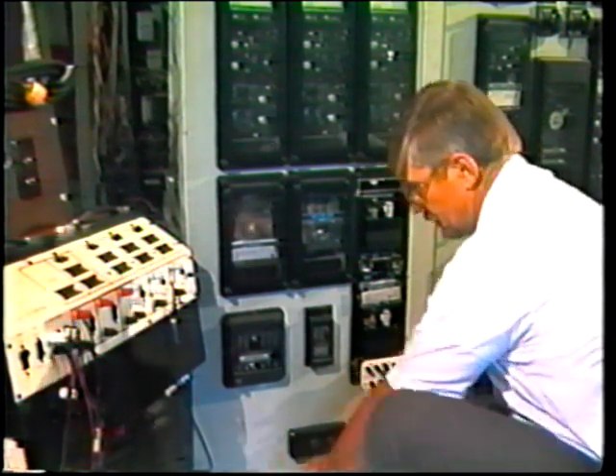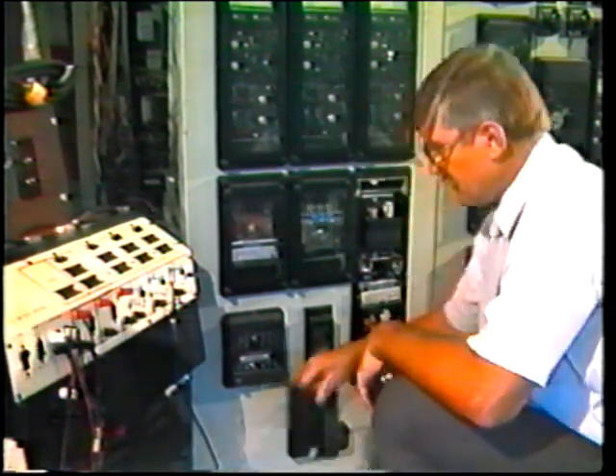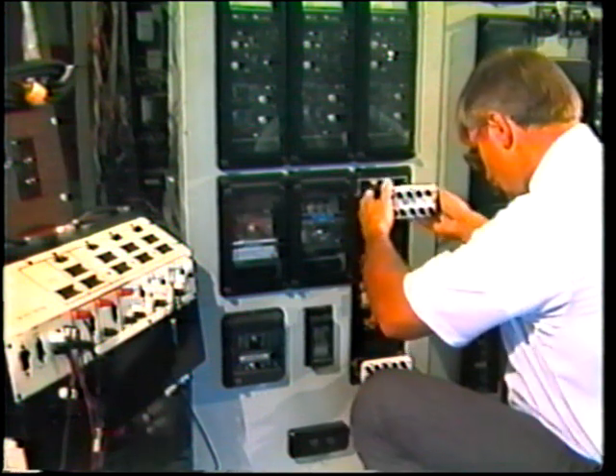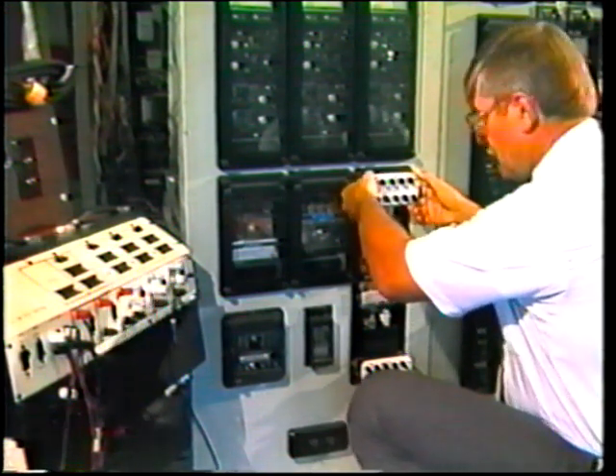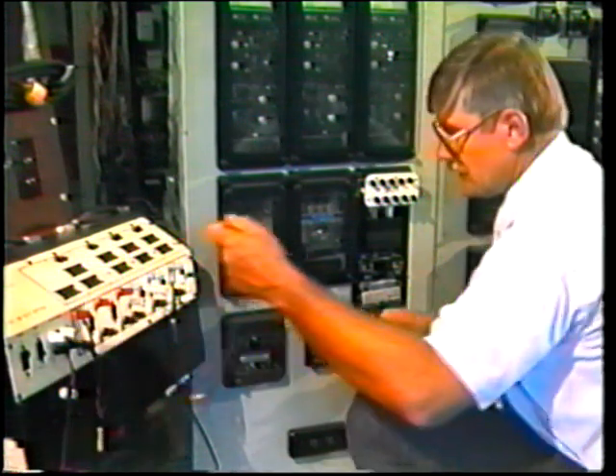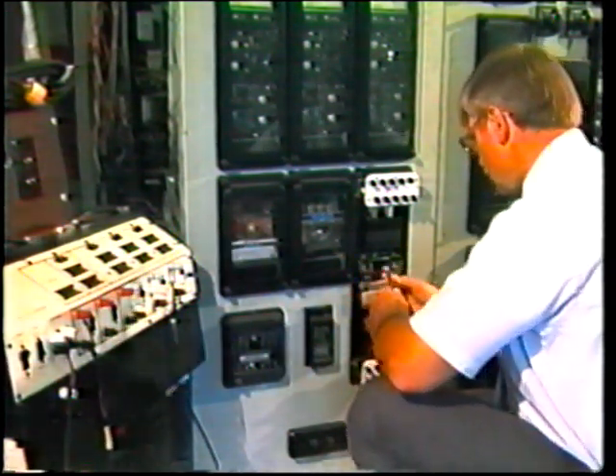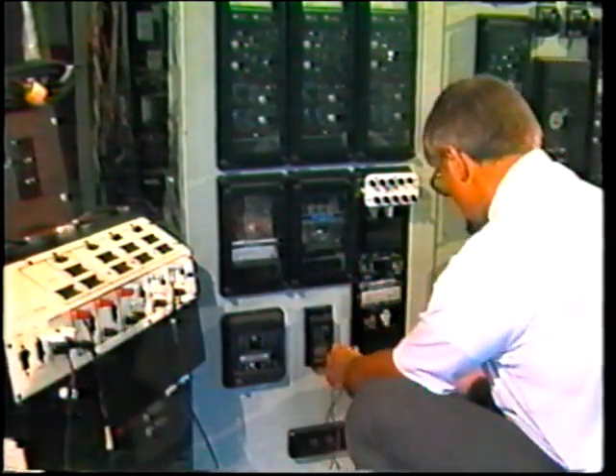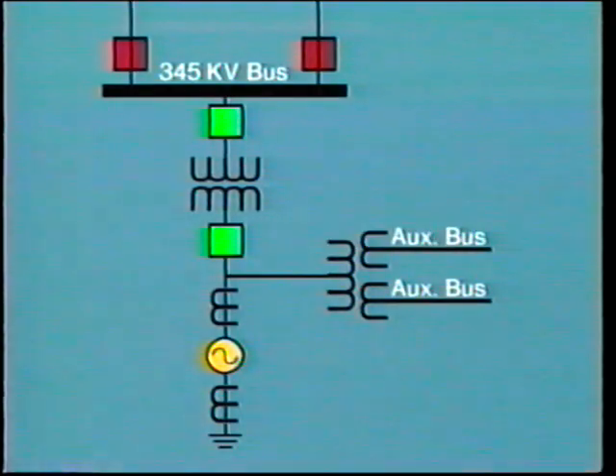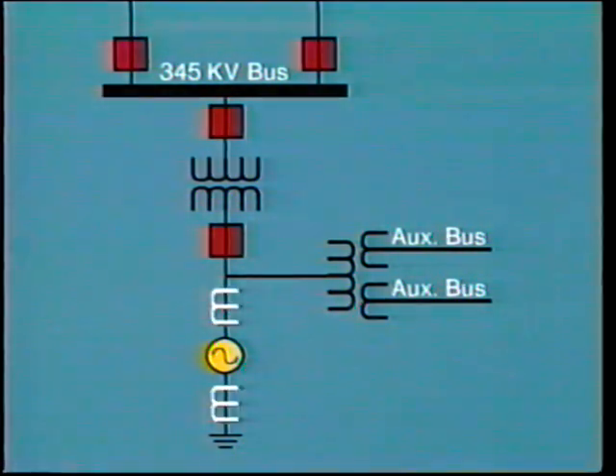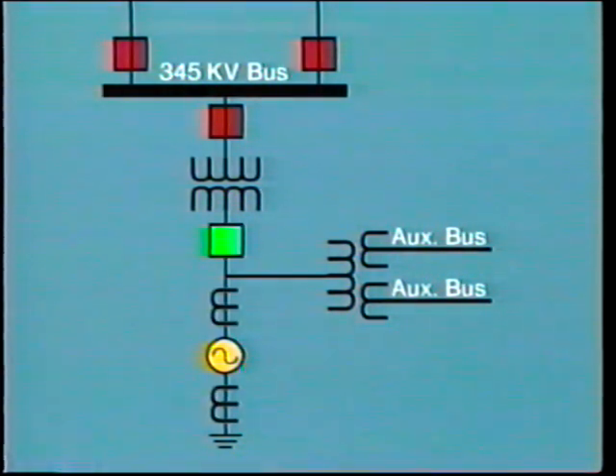Even though routine tests are less detailed than commissioning tests, we would expect to detect installation defects that may have been missed during commissioning. Just as important, routine testing will also reveal problems that may have arisen during operation. Now, our next study shows a defect which could not go undetected. This generator was being returned to service after an extended outage for modifications. As soon as the generator was synchronized to the system, the differential relay operated and tripped the unit.